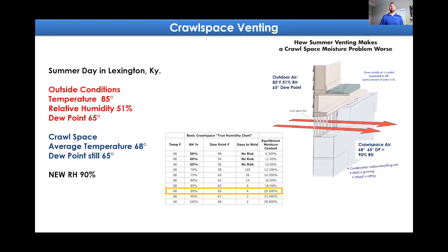So as I mentioned with crawl spaces specifically, if I took a typical summer day in that Lexington, Kentucky market, outside conditions being 85 degrees, 51% relative humidity, we might think, wow, that's a nice day outside. It's not overly humid, nice dry bulb temperature, but the dew point is 65 degrees. How do we feel in that condition? Might be a little uncomfortable. Taking that aside, if we have an old style crawl space with open vents, that air is being pulled or drawn into the crawl space and introduced to a much lower temperature. So we're squeezing that air mass into this cold air, and it starts to condense really quickly.